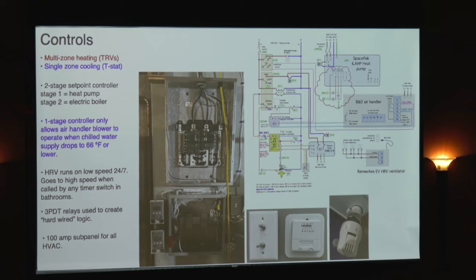One of the controls we built in here, and this is something to think about: let's say you've got an air-to-water heat pump, and it's doing cooling, okay? And in the summertime, you want to switch the heat pump from cooling over to heat that buffer tank because you want to maintain domestic hot water. You can't do them both at the same time. One of those modes has to be a priority. In this project, we made cooling the priority.